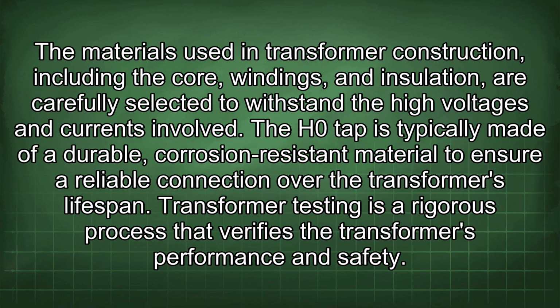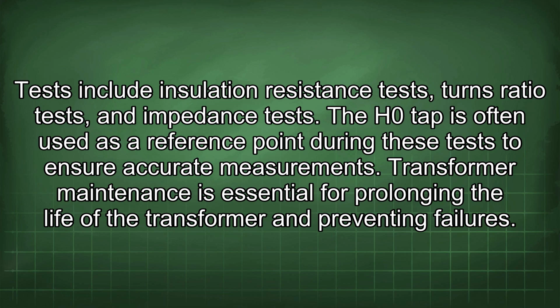The materials used in transformer construction, including the core, windings, and insulation, are carefully selected to withstand the high voltages and currents involved. The H0 tap is typically made of a durable, corrosion-resistant material to ensure a reliable connection over the transformer's lifespan. Transformer testing is a rigorous process that verifies the transformer's performance and safety. Tests include insulation resistance tests, turns ratio tests, and impedance tests. The H0 tap is often used as a reference point during these tests to ensure accurate measurements.